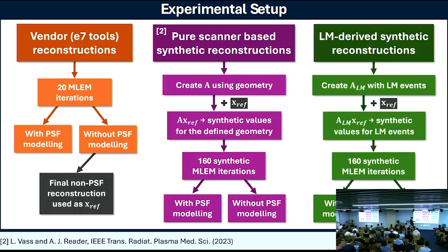We did 2D and fully 3D reconstructions, and to test the limit of our list mode derived reconstructions, we reduced the number of events that we acquired just randomly, as there is often lots of redundancies from a particular acquisition, to see how far we can go with reducing the size of our list mode derived system matrix.